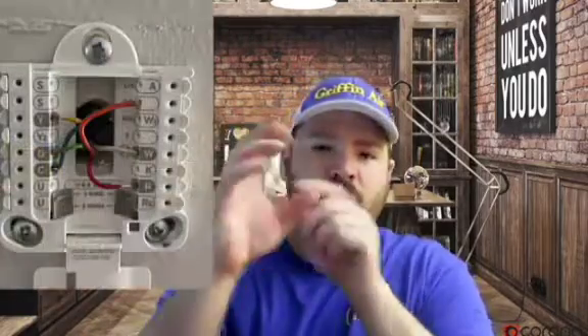One thing that can fix that is if there's a hole behind the thermostat where the wire comes through. Sometimes sealing that hole, which you can do a number of ways, can fix your issue. For example, if it's hot in the room but that hole connects to a cavity in the wall coming from, say, the basement, you might get cool air reaching the thermostat and throwing off your readings.